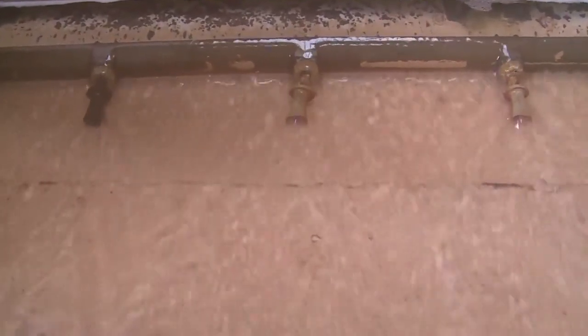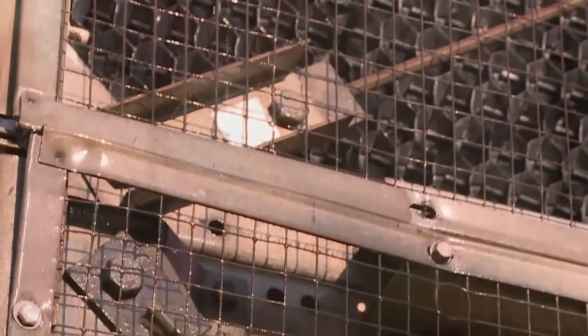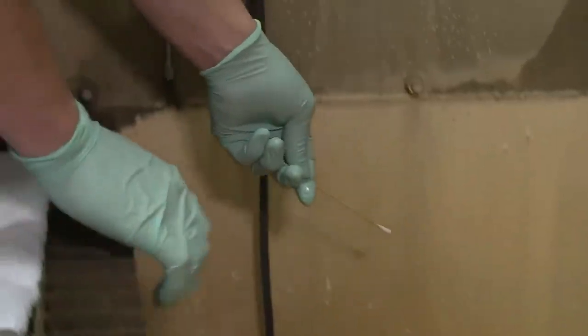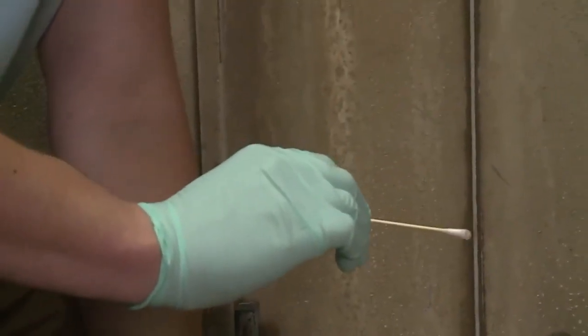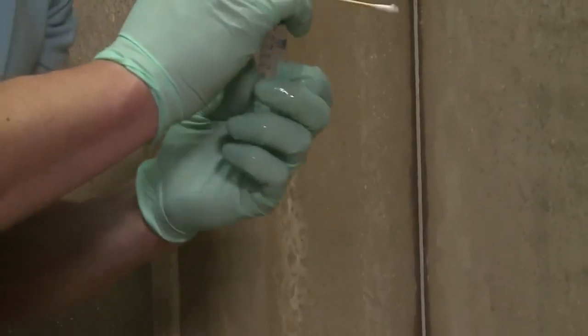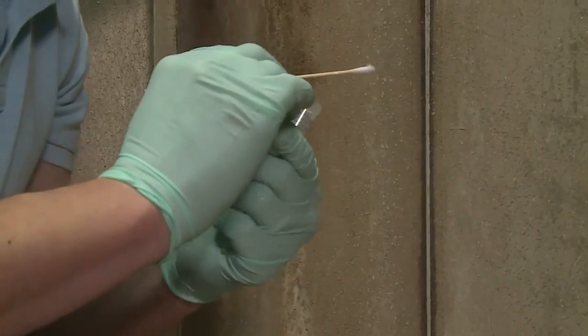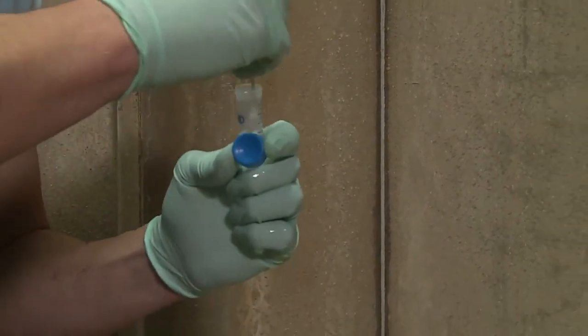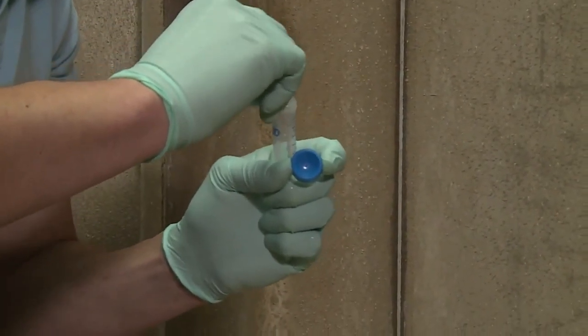Next, you will need to take several biofilm swabs from moist surfaces, such as the water line in the basin, the fill, or a drift eliminator. Run the swab firmly along the surface. Collect 3 to 5 milliliters of water associated with the source into a 15 milliliter sterile tube. The water is needed to keep the tip of the swab moist during transport.